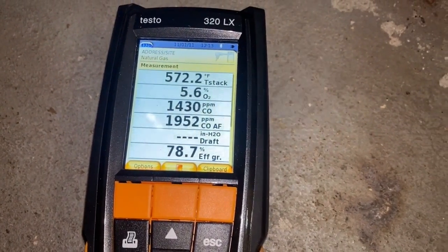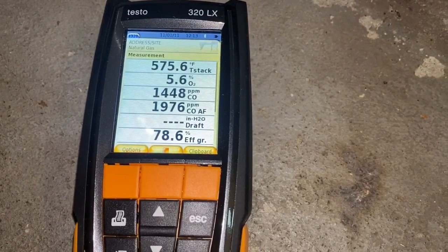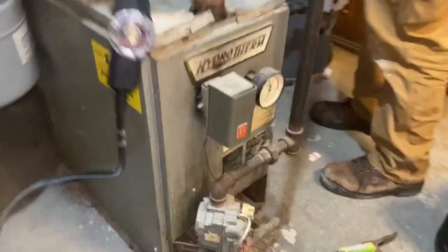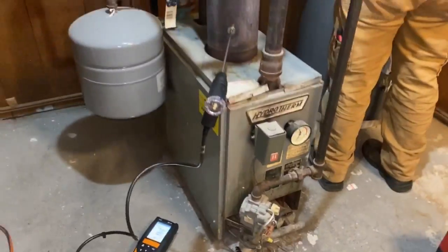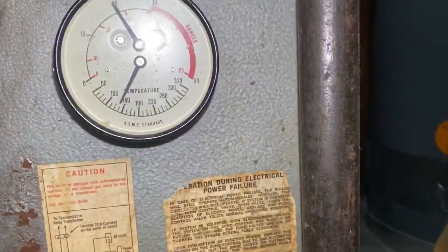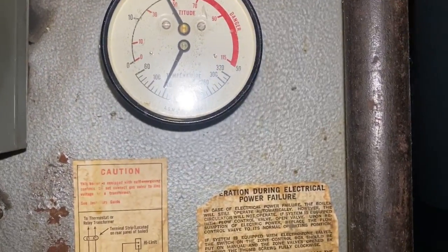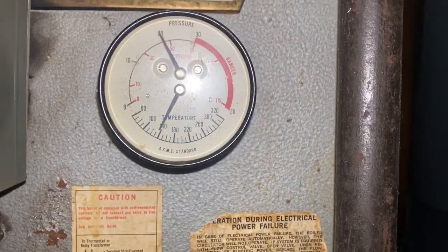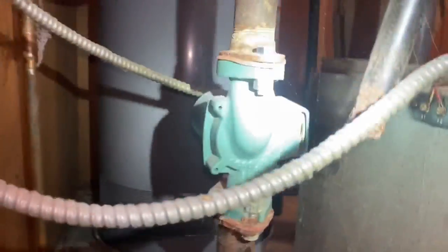Our oxygen is 5.6%, stack temperature 575 degrees, and 78.6% overall efficiency on this Hydrotherm. Let's take a look at the temperatures and pressures. Our temperature is right around 140 degrees. Pressure is right around 20. We'll confirm that by testing the pressure on the extra gauge. Make sure we have no leaks, no crazy rust going on here — which we don't. Taco 007 circulator.